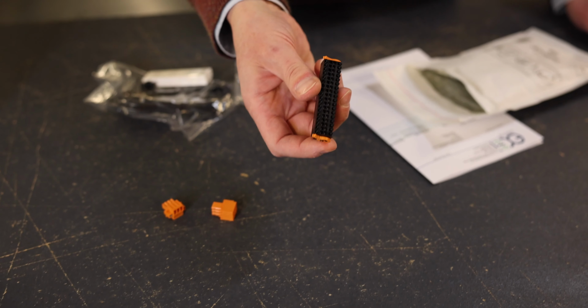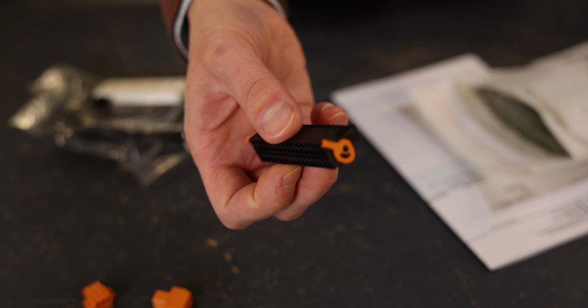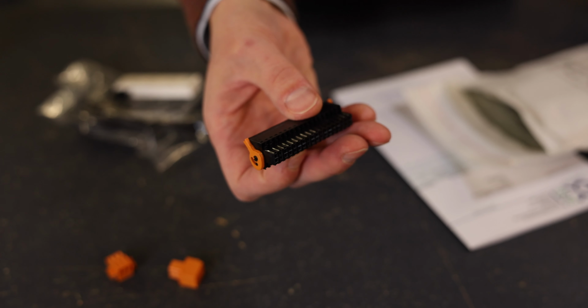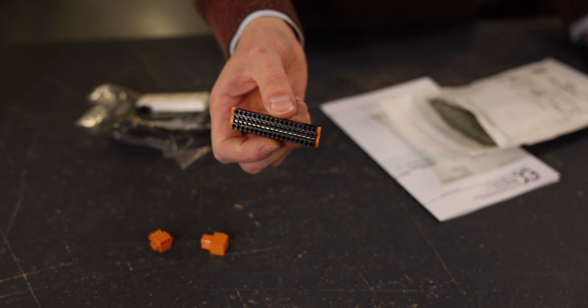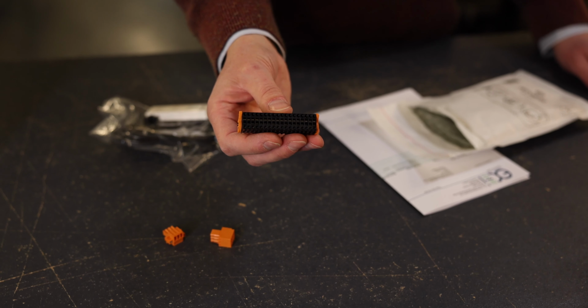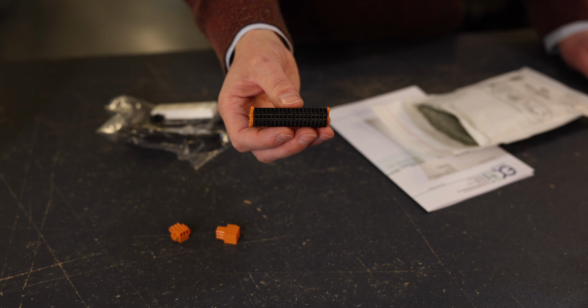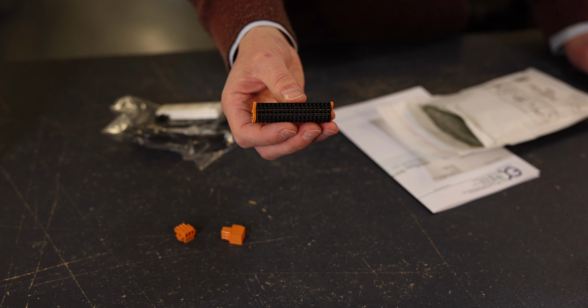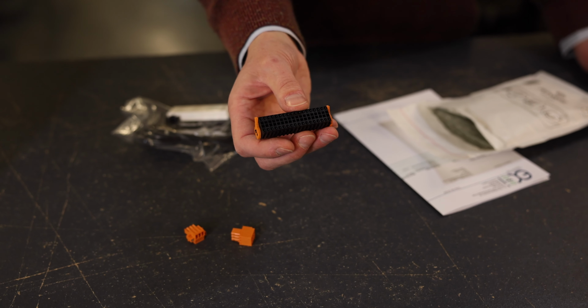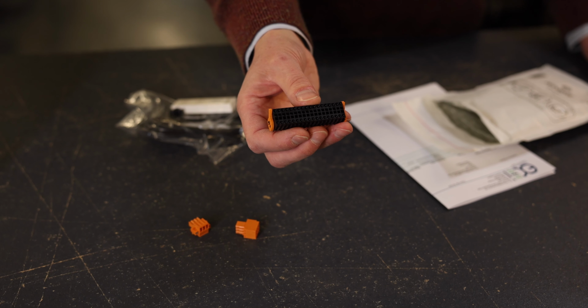Each of the optional I/O boards come with either a 36-way spring clamp style connector or a pre-made cable depending on what was ordered. The 36-way connector has a suitable wire size of 0.2 to 1 mm square without ferrules. The cable options will be discussed in a later video.